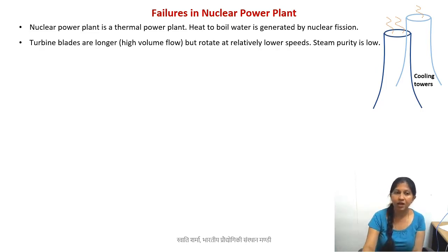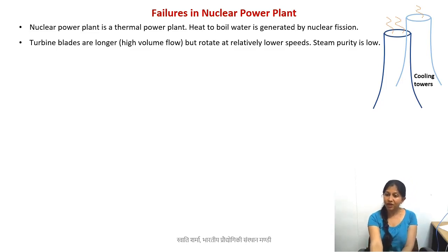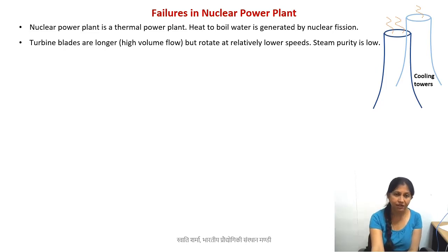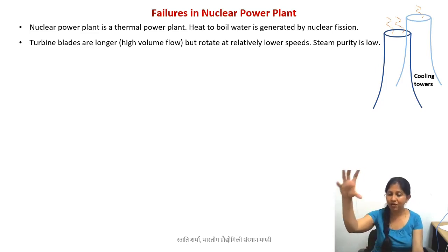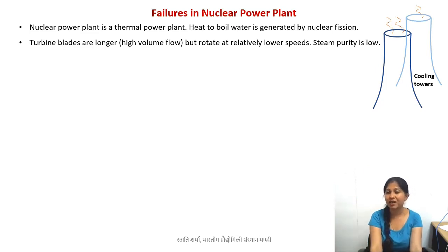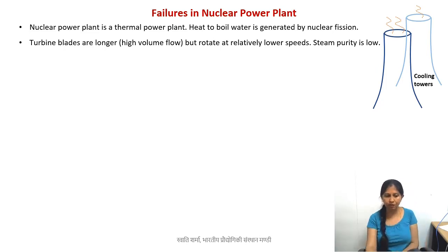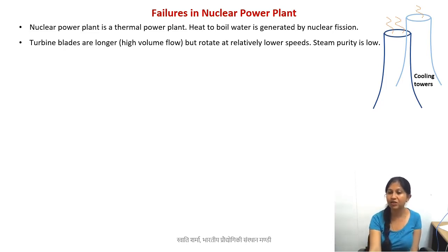Is there any difference in turbine blade design compared to a coal power plant? The answer is that the volume flow of steam in nuclear power plants is much higher, and hence the blades need more surface area — the blades need to be longer — however they rotate at relatively lower speeds. Also, the purity of the steam is lower compared to a conventional steam power plant, because there are water droplets mixed in the steam; it is a low-temperature steam, also called wet steam.